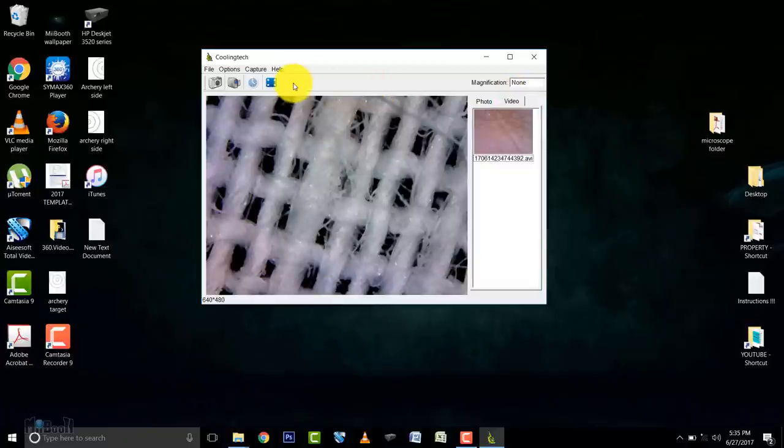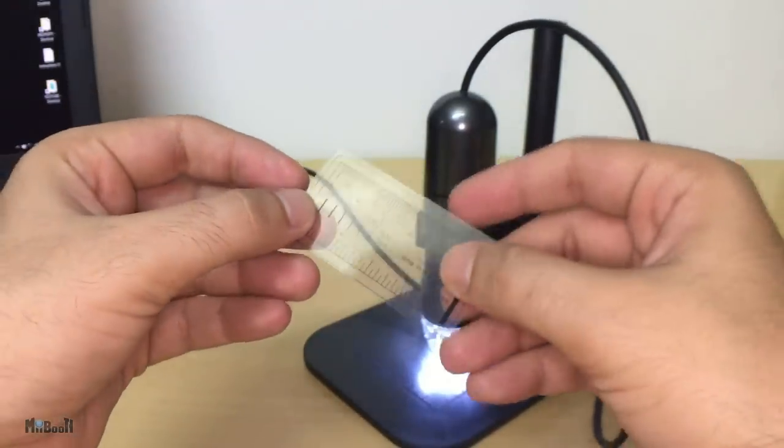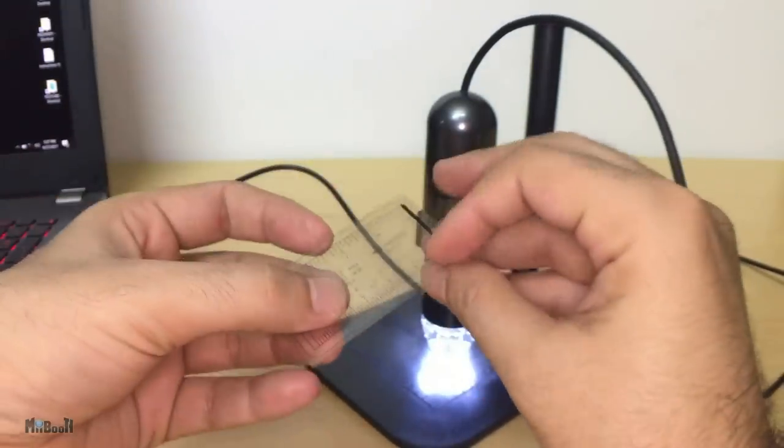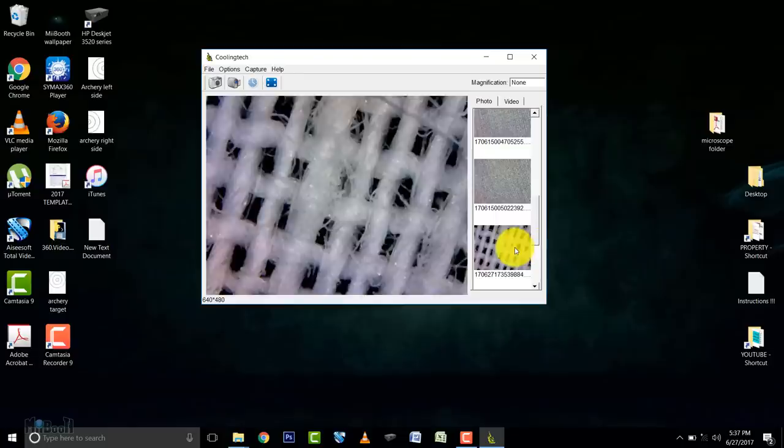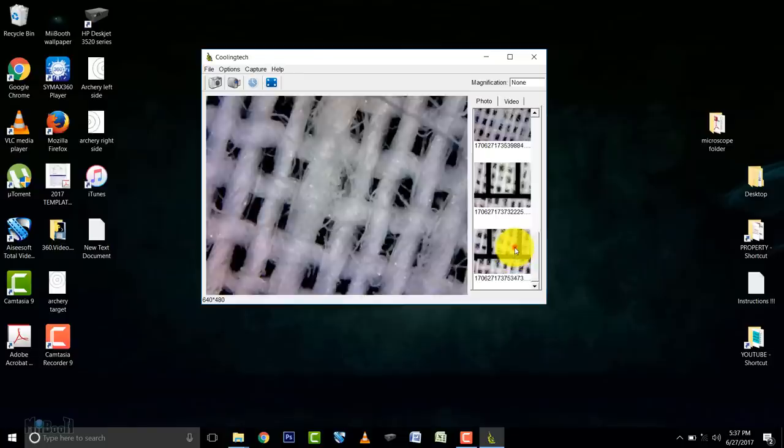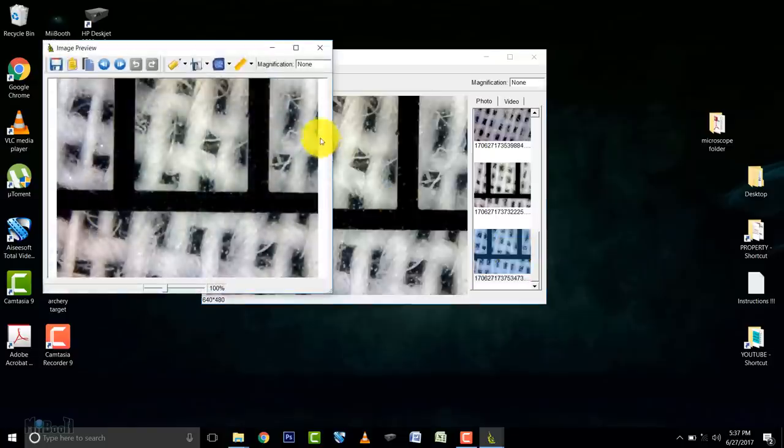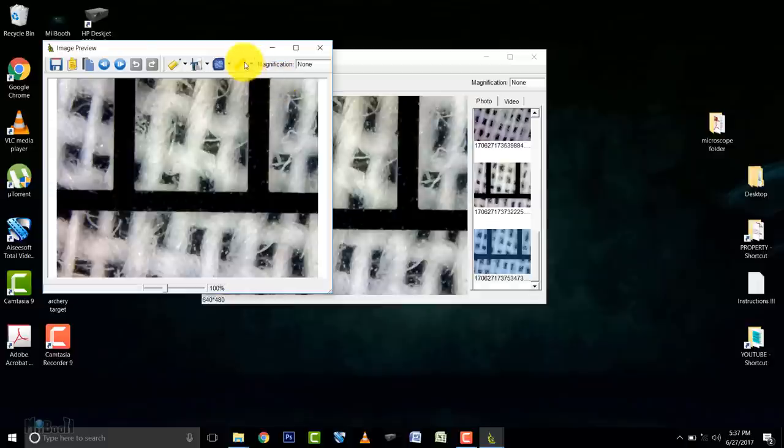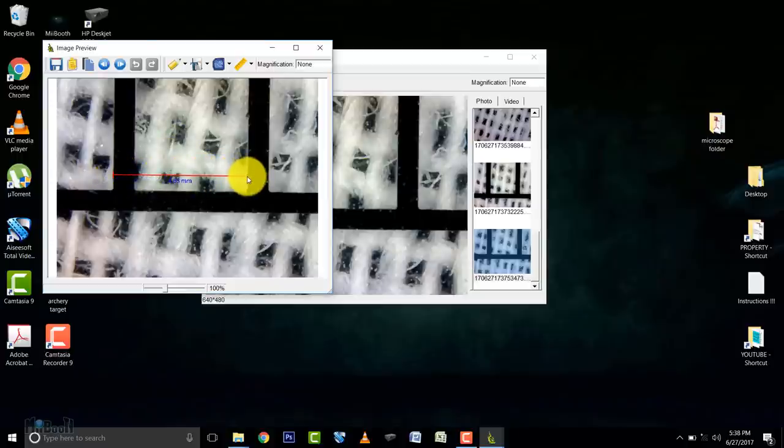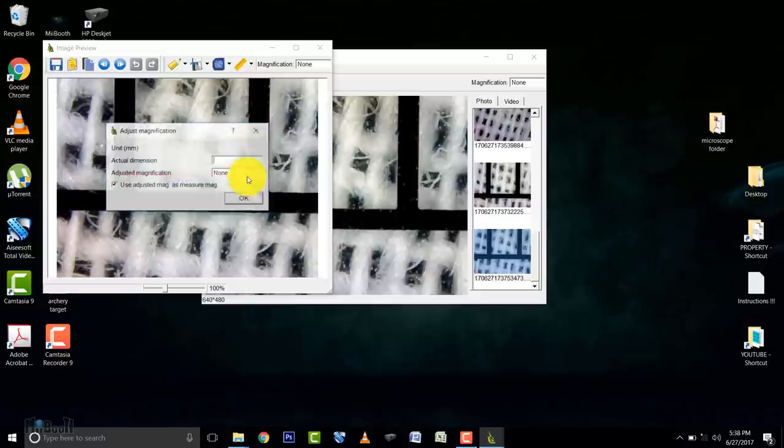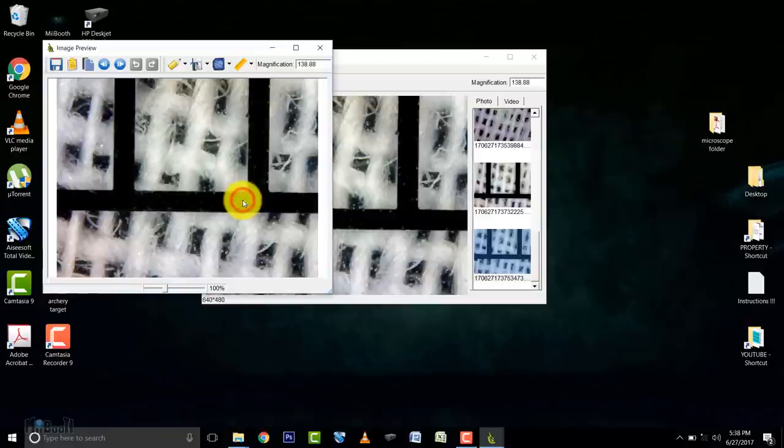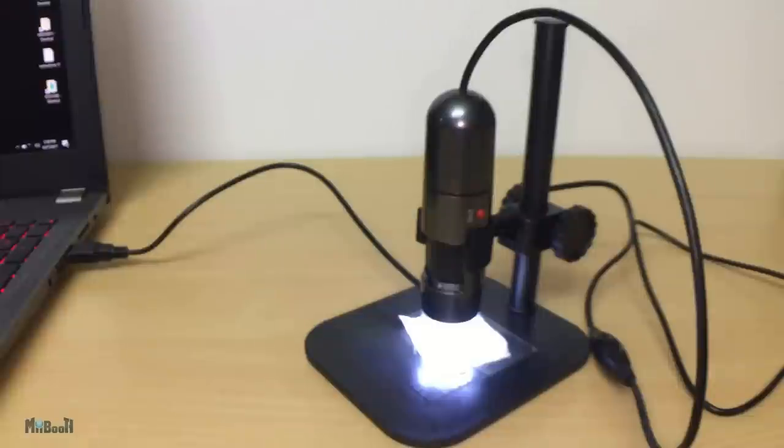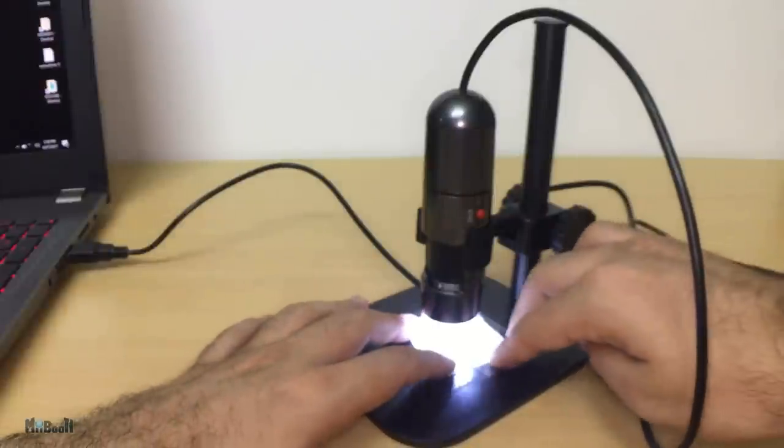So you take the calibration ruler, place it beneath the microscope. I'm going to go for max zoom. When the image is crisp and clear, I'll go ahead and take a picture. Now double click on the picture, click on the ruler icon, and click calibration. Since I know this distance is one millimeter from the ruler, I will click on one end, drag the line till the other end, and release it. A window will pop up. It will ask for the actual distance. I will enter one. The increments are set to millimeter by default in the settings.